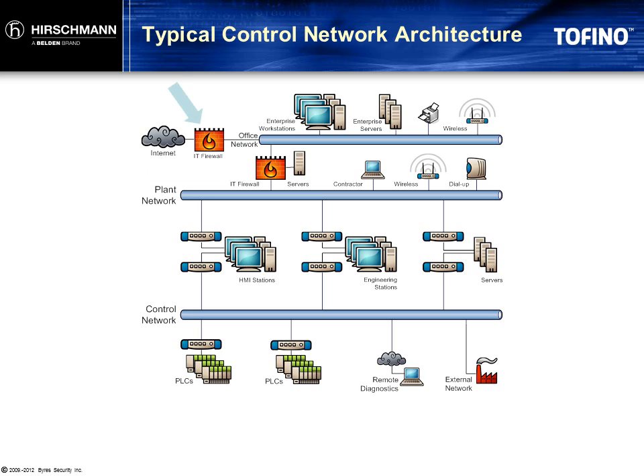If properly configured, the firewall on the plant network will be able to stop cybersecurity threats that originate from the internet or the enterprise network. But what happens if a contractor brings a laptop into the plant and that laptop has a virus on it? One of the things that malware frequently does is to begin scanning the network, looking for other vulnerable PCs that it can infect. This scanning behavior can fill the network with so much unwanted traffic that there is no bandwidth available for legitimate traffic to pass.